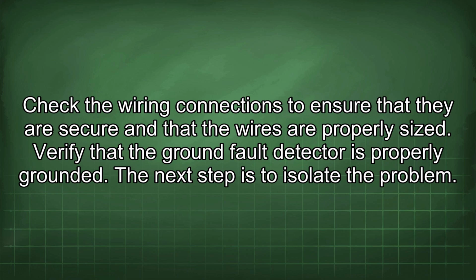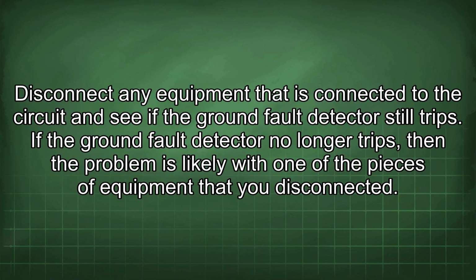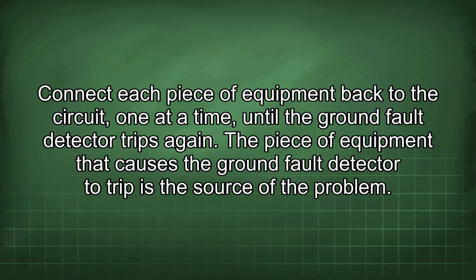The next step is to isolate the problem. Disconnect any equipment that is connected to the circuit and see if the ground fault detector still trips. If the ground fault detector no longer trips, then the problem is likely with one of the pieces of equipment that you disconnected. Connect each piece of equipment back to the circuit one at a time until the ground fault detector trips again.